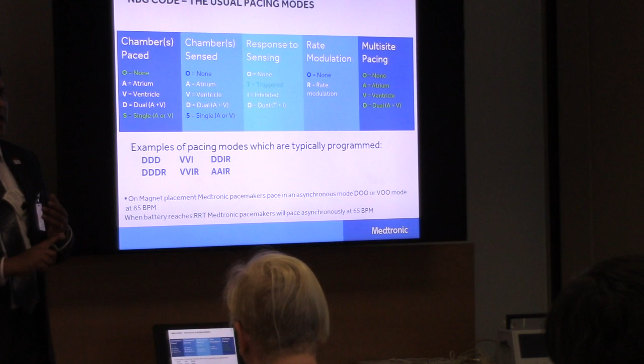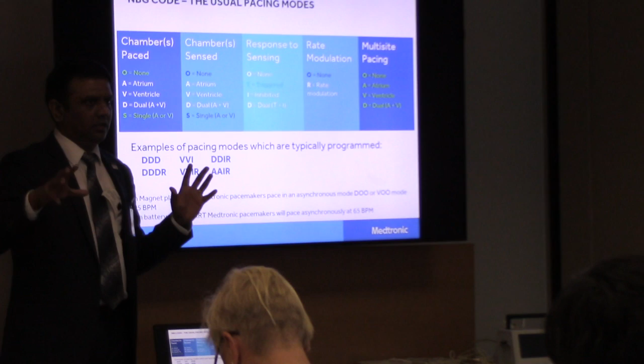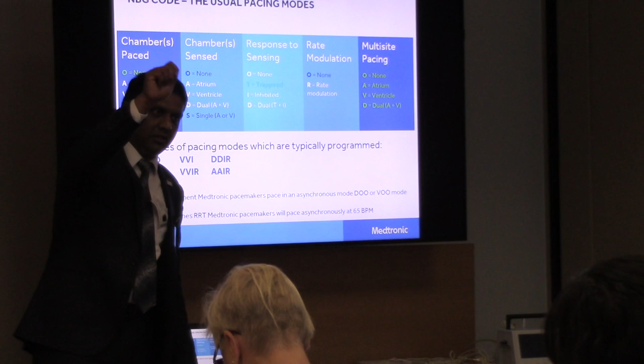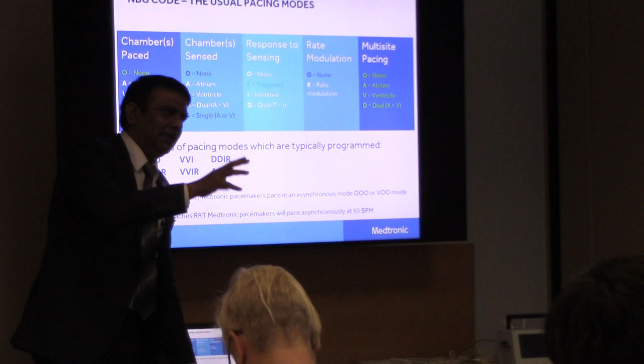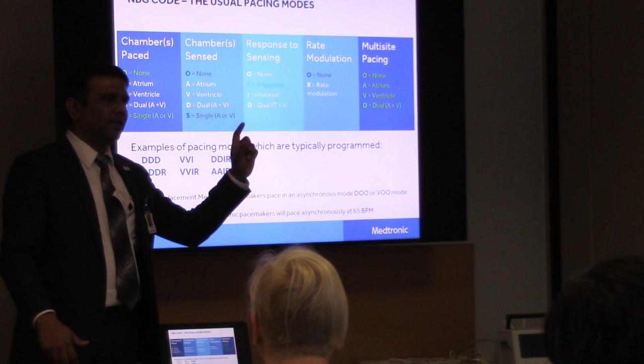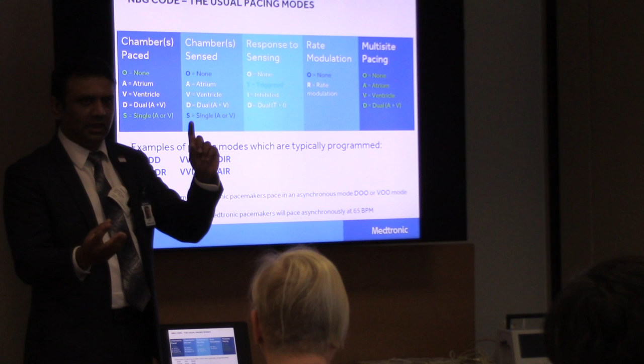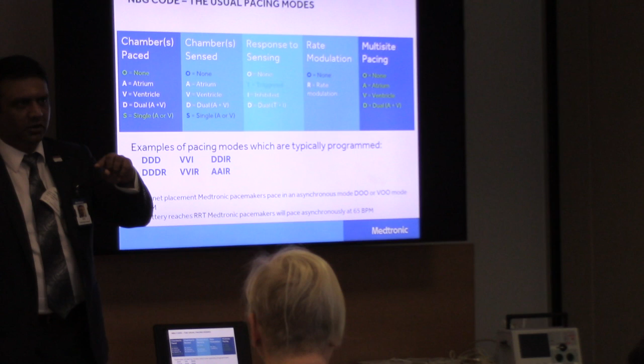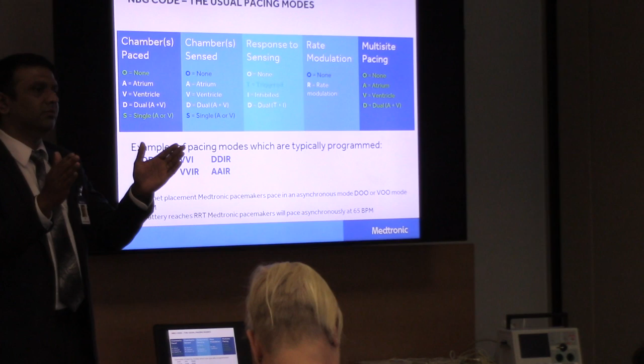Because remember that cell-to-cell conduction is slower than the normal conduction system, because you're capturing a whole big region of the heart and you're not going through the typical His-Purkinje system for your conduction to be fast. You're relying on cell-to-cell conduction, which is much slower. So that is why your paced AV delay would always be higher than the sensed AV delay. So if you're sensing an atrial event, you will trigger the ventricle a little faster than when you're pacing an atrium. Okay? Because you're assuming that the sensed pulse went faster to the AV node, and therefore you can trigger now, like you would put that time a little faster, okay?